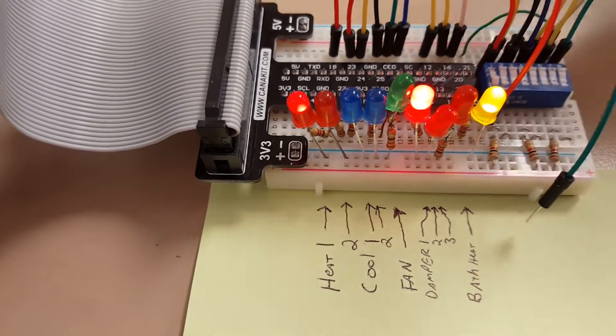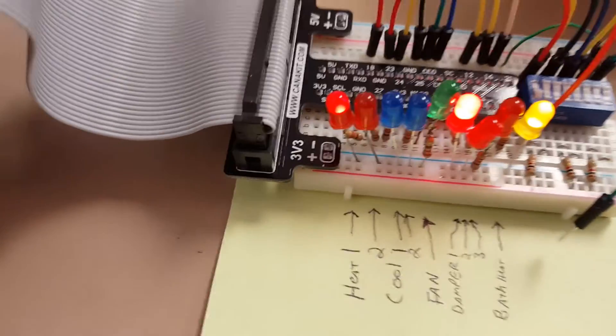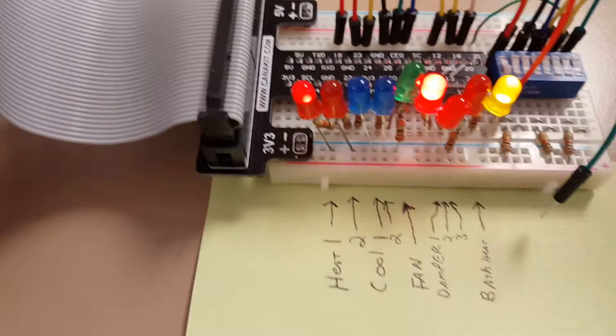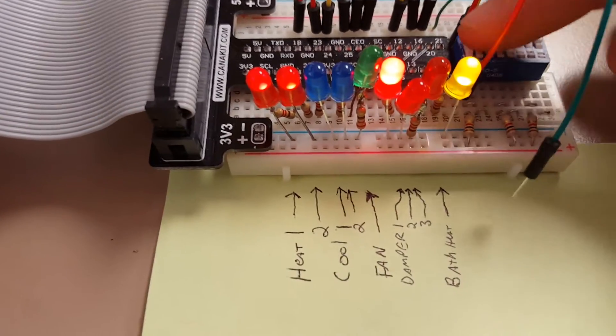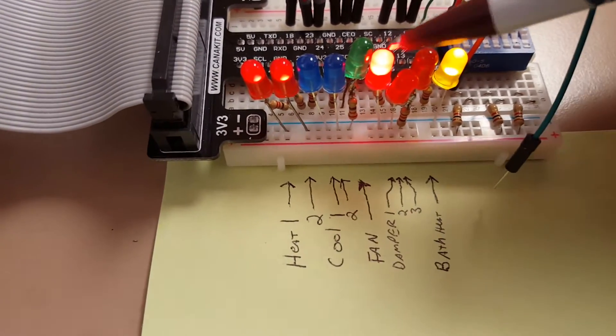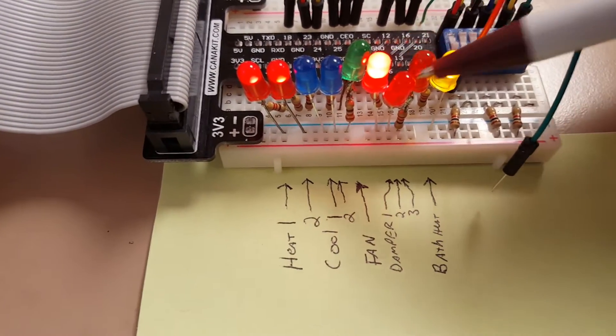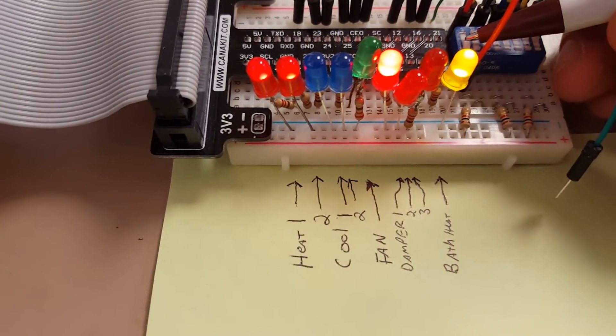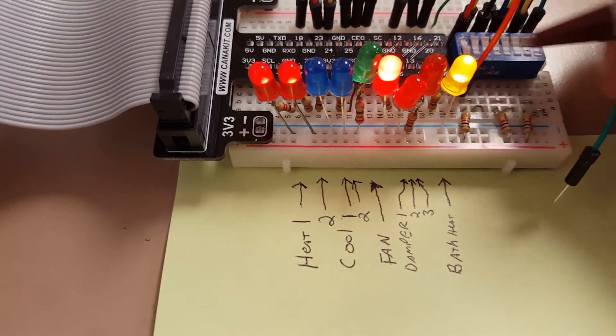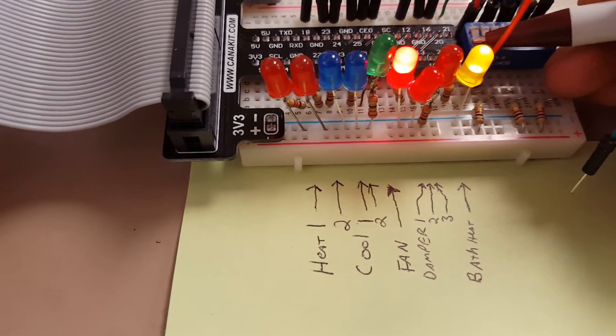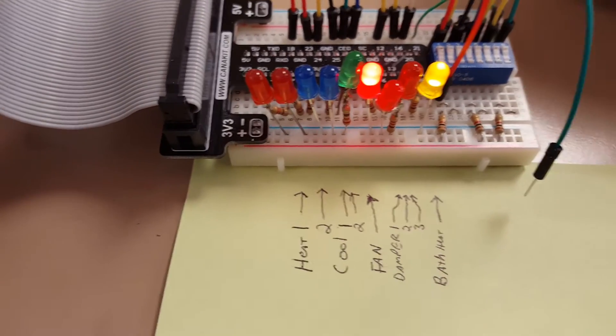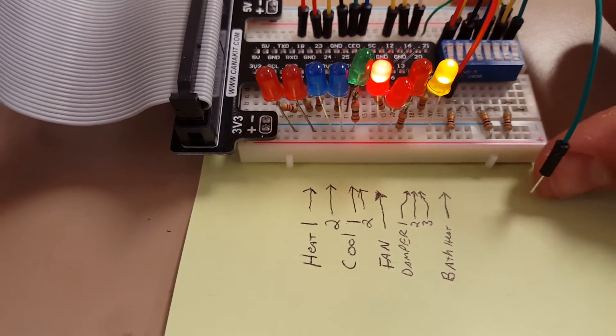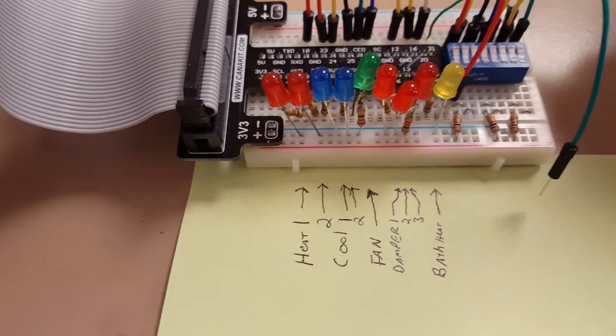The other thing you'll see is a delay in the zone dampers. The last one will stay open for a short time after the heating is satisfied, and that's just to make sure the heat exchanger can cool off before the damper closes.